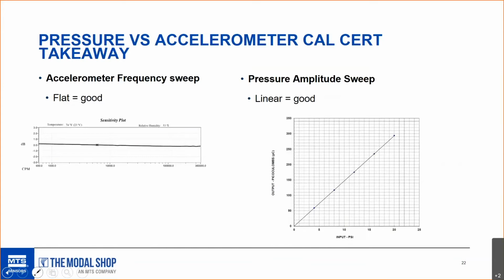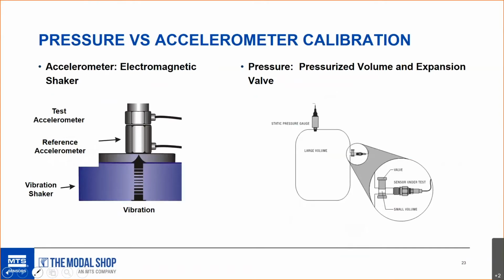And just looking at the CalCERTs between the two, the thing we're looking for on our accelerometer sweeps is a flat line across the frequency spectrum. And on pressure sensors, we want a linear line, no bend in the curve. That's really what we're looking for. So moving on, the two types of calibrations we do look like this.